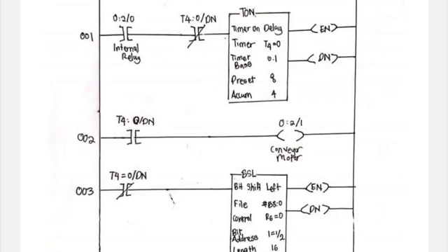The PLC program for bottle capping is as follows. Based on the PLC ladder diagram, rung 001 and rung 002 are used to operate the conveyor motor. Assuming it takes 0.5 seconds to cap a bottle, capping is performed when the conveyor is stopped for a second. When push button input 1/0 is closed, it will energize the internal relay. Then conveyor motor output 2/1 runs for a moment and stops for a second.